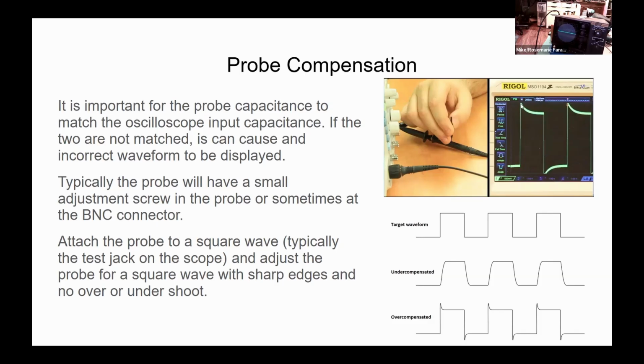Well, that means your probe isn't compensated. So you adjust it until you get a square wave. You'll either be undercompensated, where you're going to see all this roll off, or you're going to get a spike. You adjust it to get it as straight as possible. Once you get it as straight as possible, then you know that your scope is in good shape and it's going to give you a nice waveform. I don't believe you can compensate a 1x probe because there isn't anything to compensate.